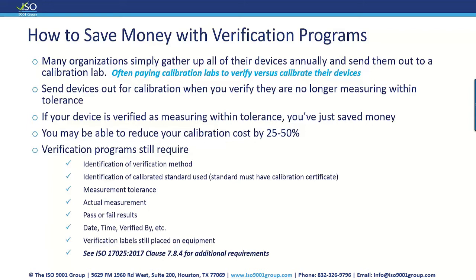Well, in many cases, the first thing the calibration company is going to do is verify that your equipment is reading properly. And if it is, they're simply going to give you another calibration certificate showing the measurement when you brought it in and the measurement after they did their work, and it's the same. You just paid the calibration lab to verify for you, which you could have done in-house yourself if you have the gauges or the standards to do that internally.